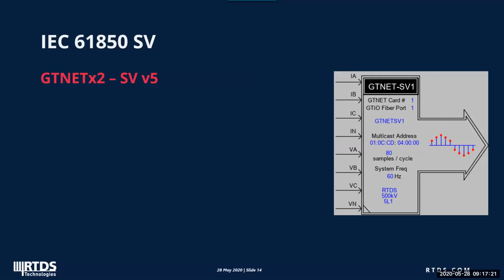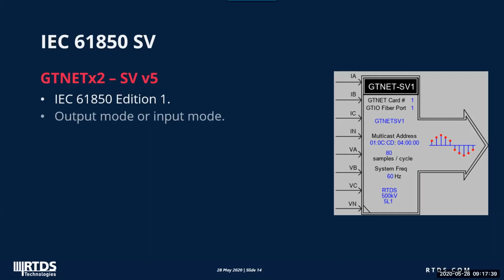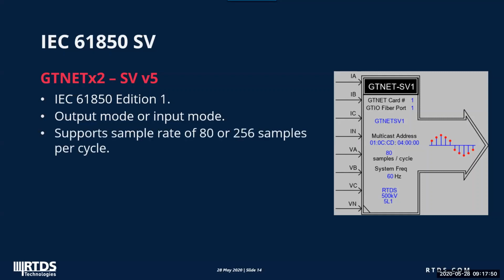Now let's move on to the sample values. There are 3 GTNet SV components available in the protection and automation library, which are V5, a special edition, and a V6. We'll just highlight the V5 and the V6 today. Now, V5 component supports edition 1 of the standard. It works either as a publisher or a subscriber, so only one mode is active at a given time. It supports sample rates of 80 or 256 samples per cycle.